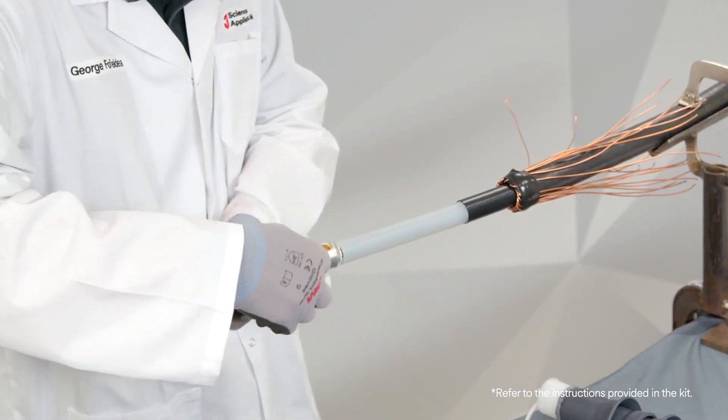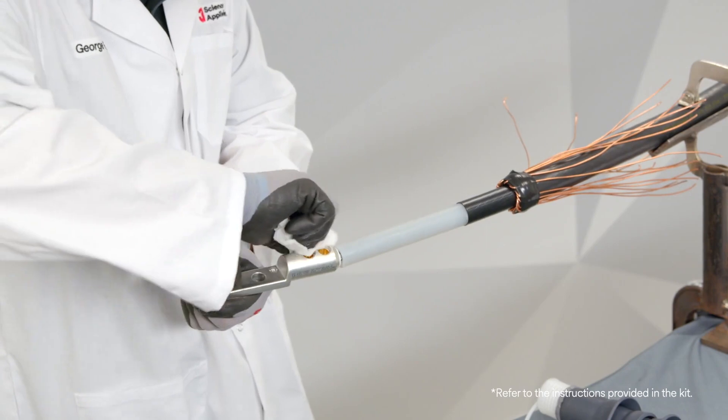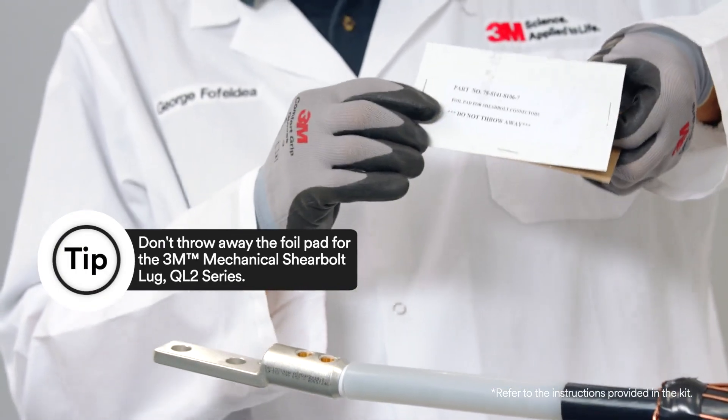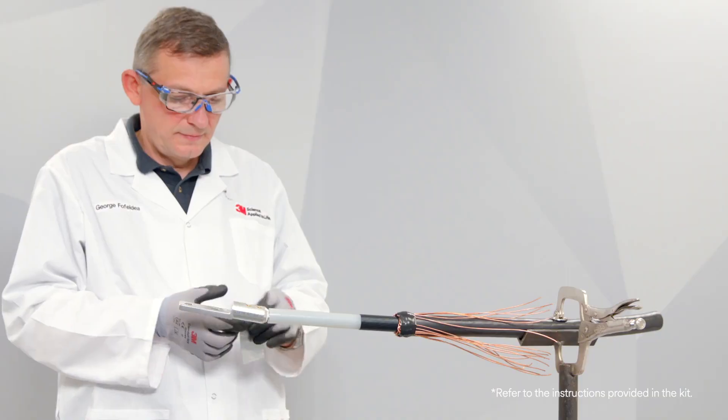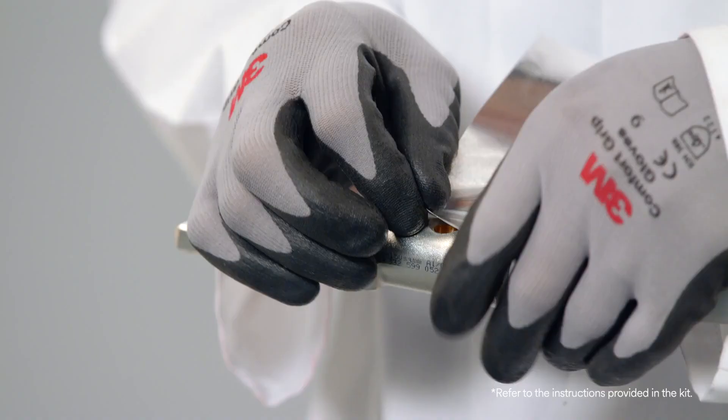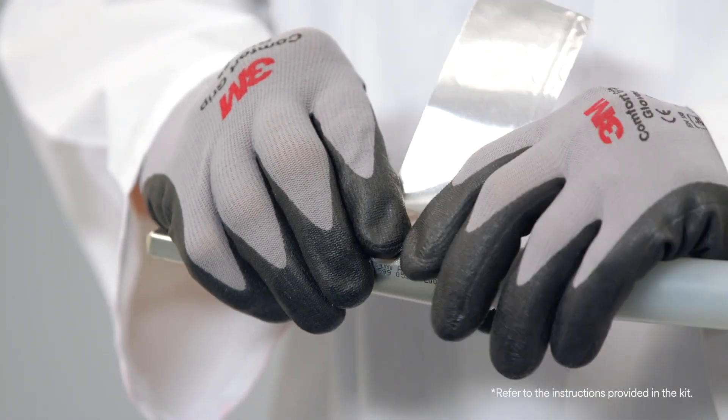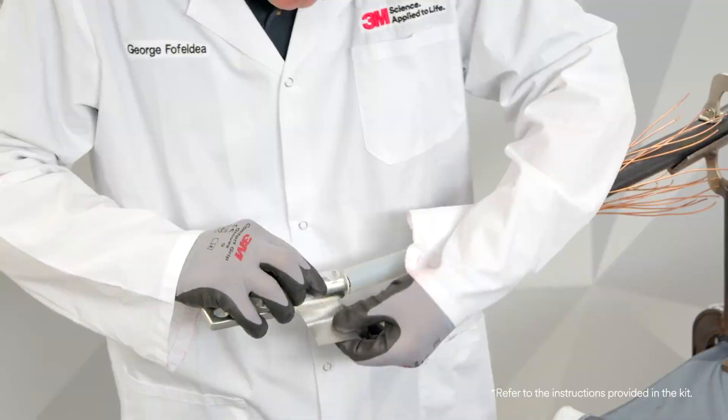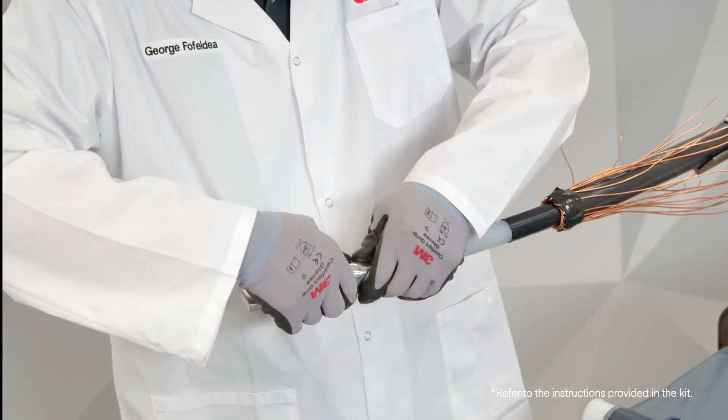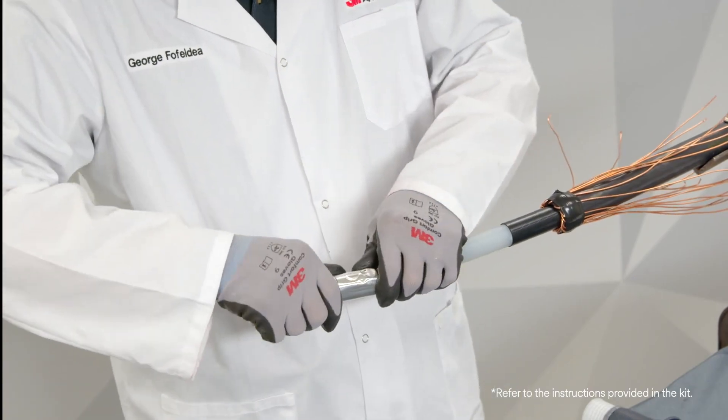To help remove any debris or grease clean the surface of the lug with the 3M cleaning solvent CC series. After the solvent is dried apply the 3M aluminum foil tape around the lug until it covers the bolt wells with a second layer. Press down the ends of 3M aluminum foil tape at the final edge and near the lug tapers.